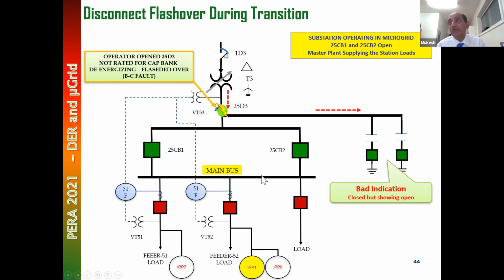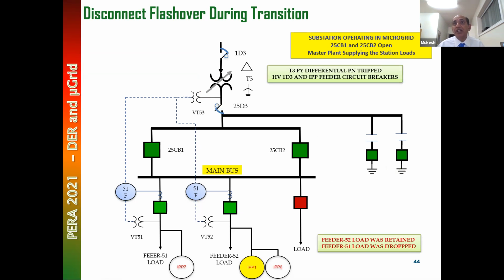So since then we have become smart. We say if these two breakers are open, we don't need to open this. We can put in a new logic, but that logic was not there. We could have had a logic: if these two breakers are open, let's not open this breaker. But that was not the logic. So that's the fault and that mistake happened.